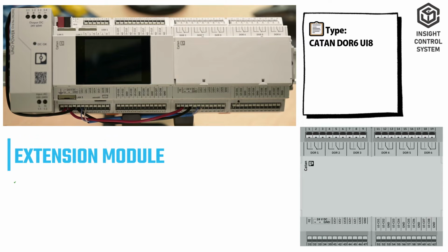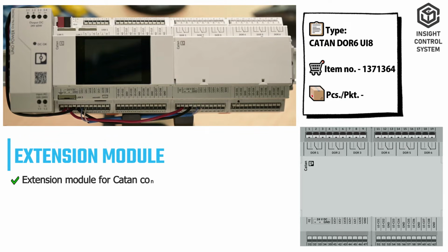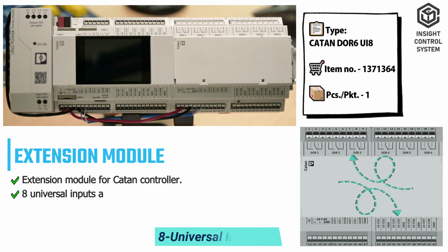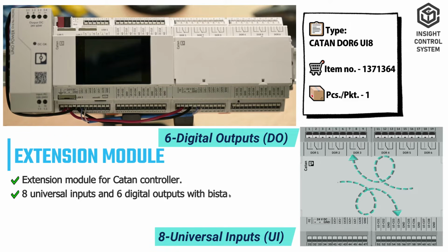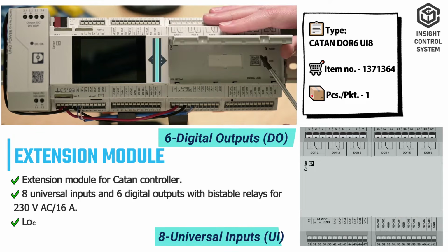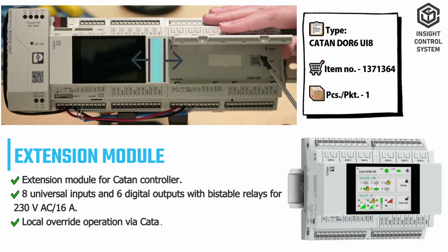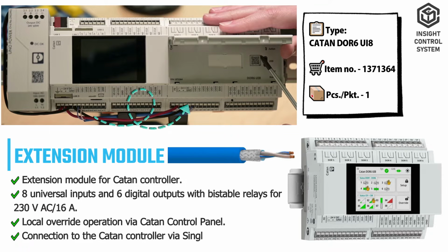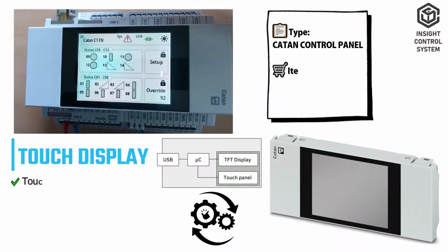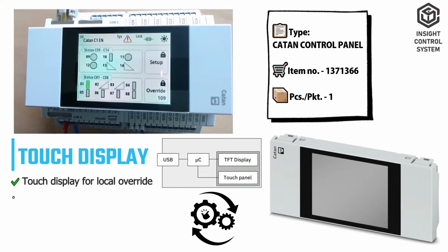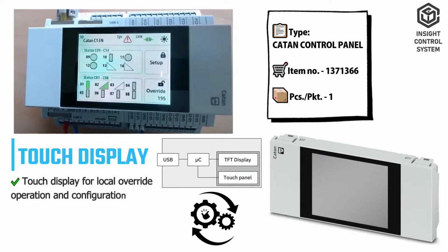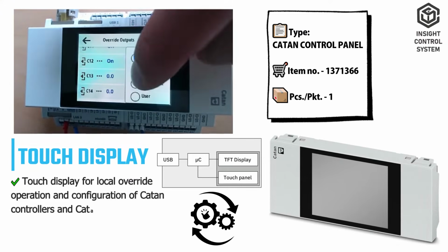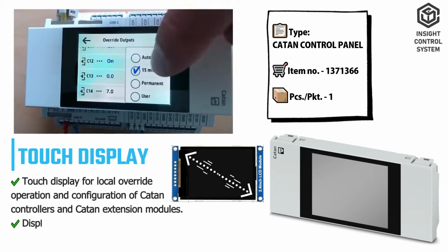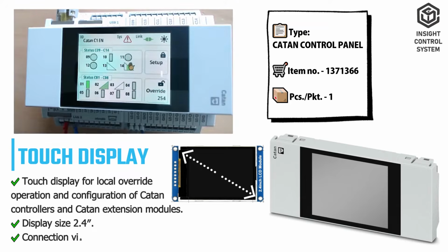Accessories. I/O module: extension module for CATAN controller with 8 universal inputs and 6 digital outputs with bistable relays. Local override operation via CATAN control panel. Connection to the CATAN controller via single pair Ethernet. HMI: touch display for local override operation and configuration of CATAN controllers and CATAN extension modules. Display size is 2.4 inch.